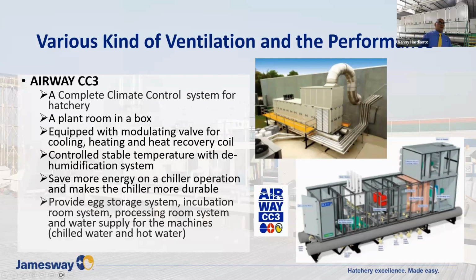It also features a dehumidification system. So it really helps, especially in places with very high humidity outside. It can reduce a lot of humidity from the environment. This machine will also provide chilled water and hot water for the incubator. And it will utilize the return water for the heat recovery coil, so it will save the energy consumption for the chillers.